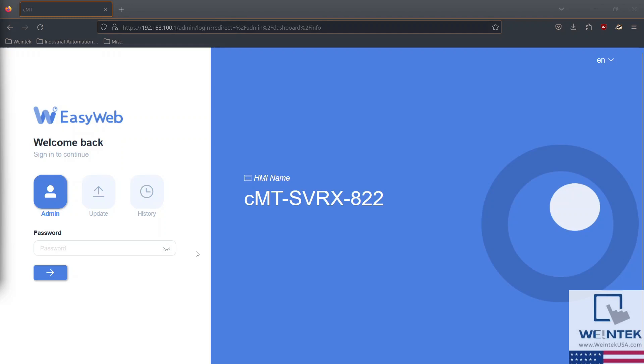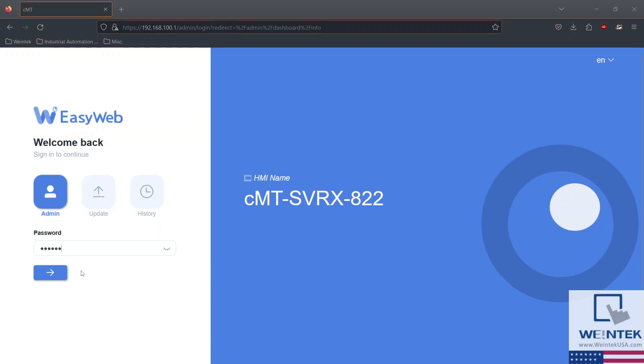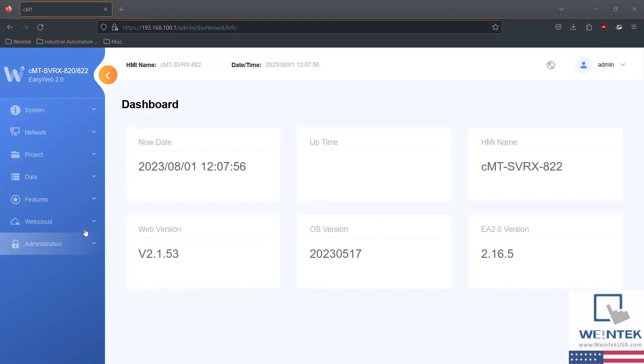Finally, we've got our cMT-SVRX-822. To view our EasyWeb dashboard, you'll need to enter the device's IP address into your browser's address bar. The default IP address for Ethernet port 2 is 192.168.100.1. Next, you'll be prompted to enter your device's password. 111111 is the default password for all Weintek HMIs.